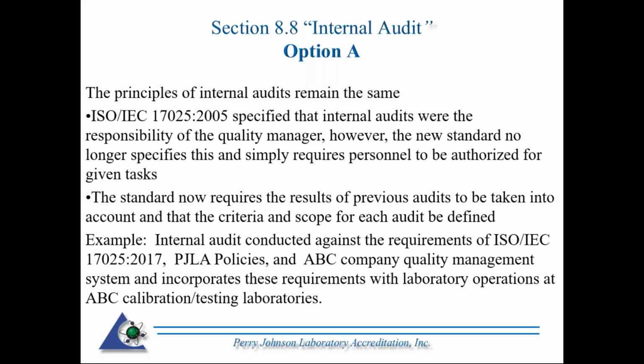A couple of differences: in 2005, it was specified that internal audits were the responsibility of the quality manager. However, the new standard no longer specifies this and simply requires personnel to be authorized for the given task. So we'll resort back to Section 6.2 on personnel here, because when we talk about personnel in the 2017 standard, we're talking about all laboratory personnel, not just the folks doing the testing, calibration, or sampling within your organization. The internal auditor would also fall into that group.